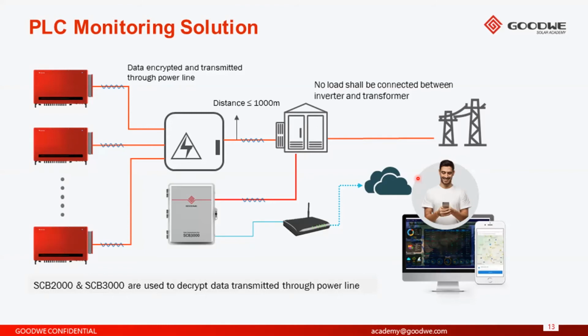However, one of the disadvantages is that PLC is usually mostly suitable for large-scale PV plants. This PLC solution doesn't typically work well with commercial installations or industrial customers because of the number of loads that they have. PLC communication, regardless of whether it's a GoodWe solution or a Huawei solution and so on, is typically for large-scale PV plants which have very small and very light loads on site.